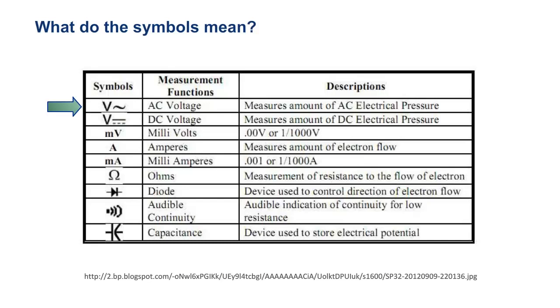One question I always get is, what should the reading be? If you're expecting 230 volts, remember it can be plus or minus 10%. So if I'm measuring 219, 220 on a 230 volt system, that's not critical. A better question is, keep measuring it when the pump starts. If that 220 suddenly drops down to 190, 200 volts, we have a bigger issue. It could be wire sizing, it might be a bad breaker. You might need to get an electrician involved.